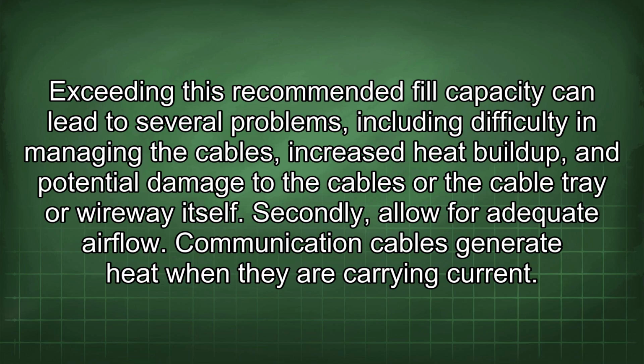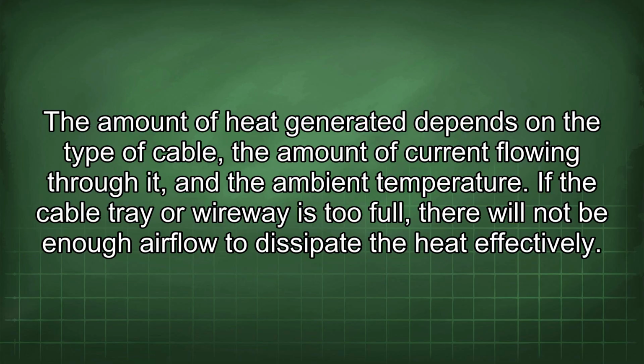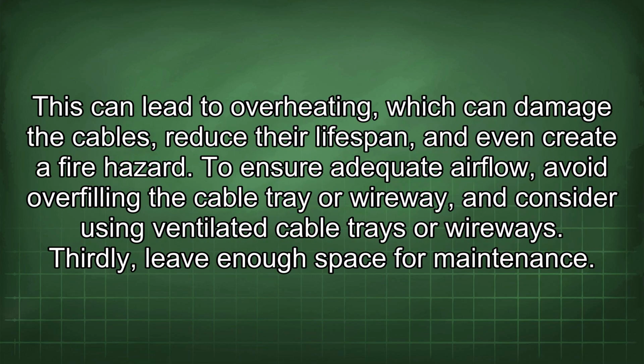Secondly, allow for adequate airflow. Communication cables generate heat when they are carrying current. The amount of heat generated depends on the type of cable, the amount of current flowing through it, and the ambient temperature. If the cable tray or wireway is too full, there will not be enough airflow to dissipate the heat effectively. This can lead to overheating, which can damage the cables, reduce their lifespan, and even create a fire hazard. To ensure adequate airflow, avoid overfilling the cable tray or wireway, and consider using ventilated cable trays or wireways.